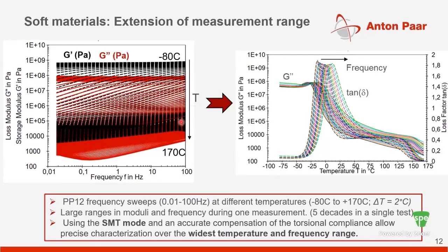And this is some data generated on an SMT type device, where I'm showing you frequency sweeps done at a bunch of different temperatures from -80 to 170 C in 1 centigrade intervals. You can see there's a bunch of different data here. And the characterization across the entire frequency space of the rheometer, which typically has specs of 100 hertz, you can see how you can characterize the materials completely till 100 hertz. This will be very difficult to do if you just have a CMT device, where typically once you start going low in modulus and at high frequencies, you see this spurious increase, which I was talking about earlier.